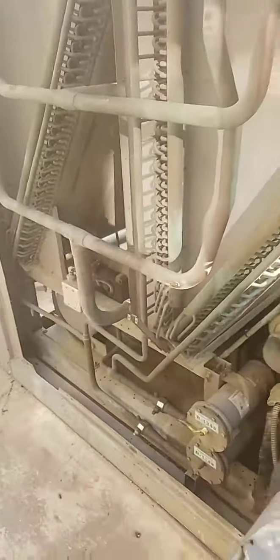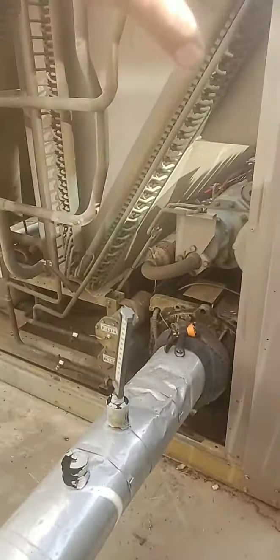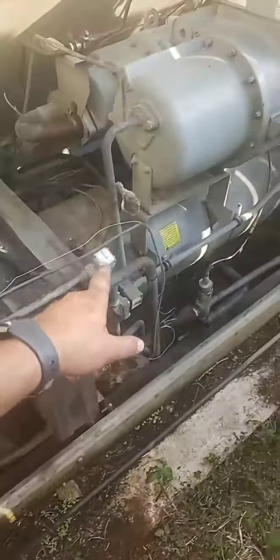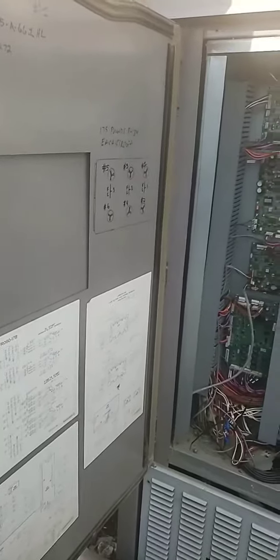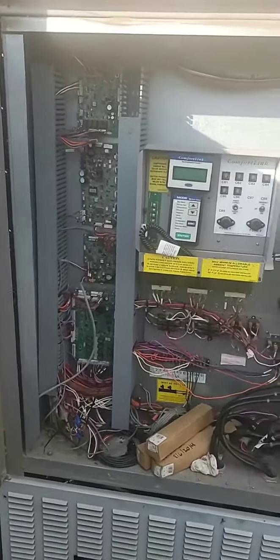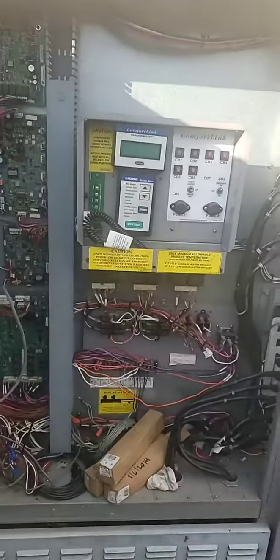Let's see, that's a basic overview of the system itself, going from the compressor back to our economizer, our motor cooling, our EXV, all the way back around to our oil separator. So let's take a quick peek at our controls cabinet here. See if I can get this open. Hang on, I'm sorry guys, for some reason my connection. Alright, we're back. Sorry about that.